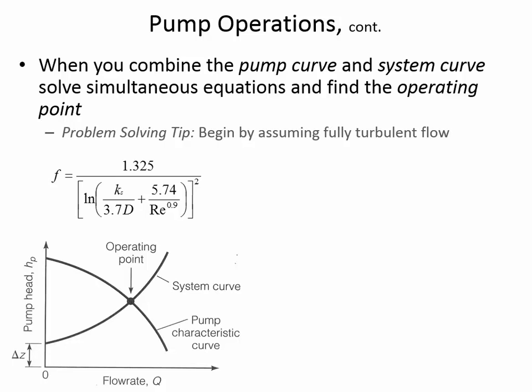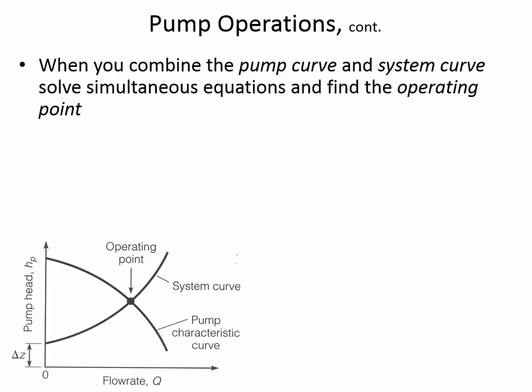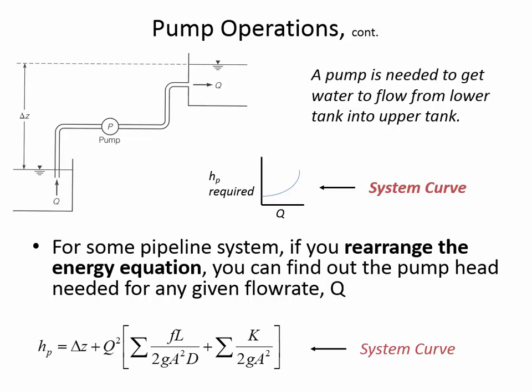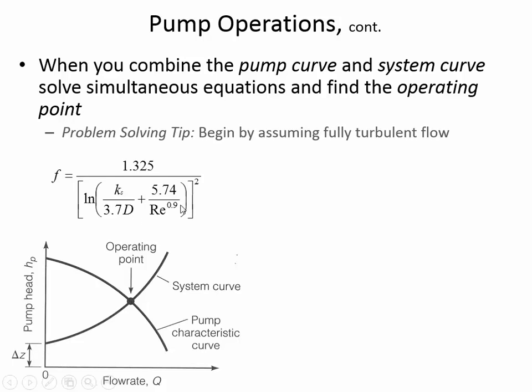So here's the Swamee-Jain equation, and what's the tricky thing about using it if we're not yet sure? Let's go back just a step. We want to use the Swamee-Jain equation so that we can find f in our frictional losses. If we don't know the flow rate yet, we can't know the f value because the f value depends on Reynolds number. And Reynolds number is a function of flow rate. So it's this endless loop of we're not sure what the flow rate is, but the flow rate depends on f value, but f value depends on flow rate, and so on. So what do we do in that case?